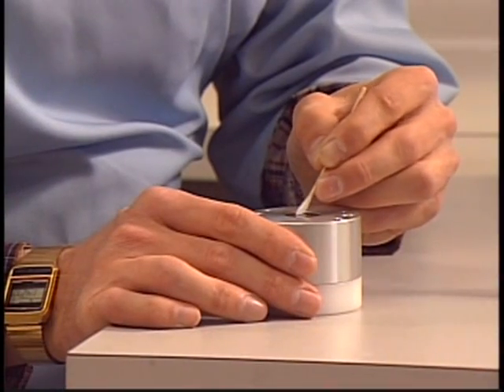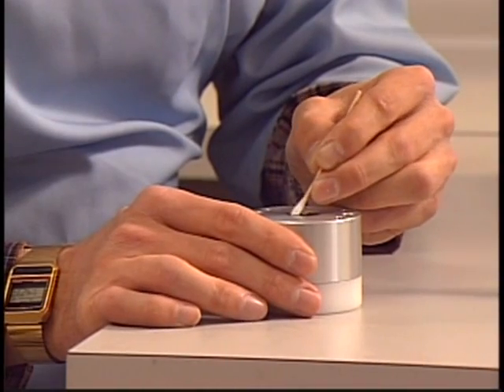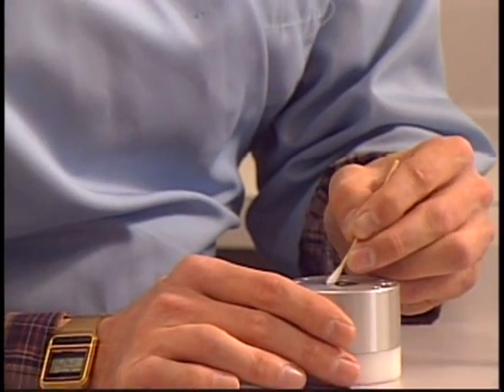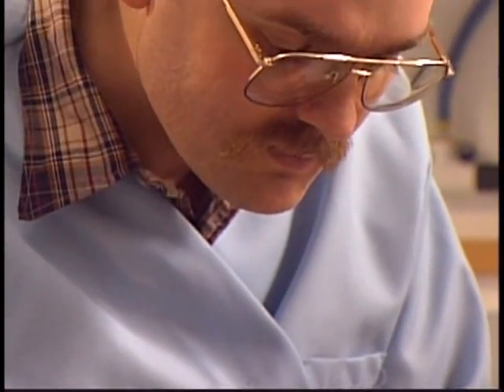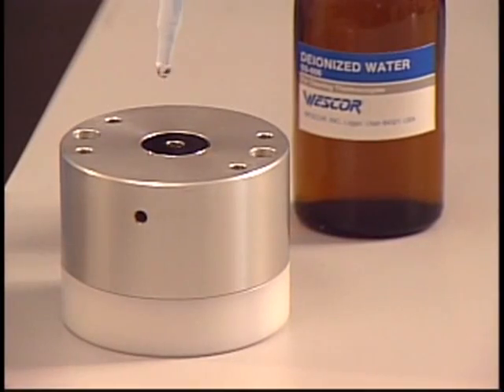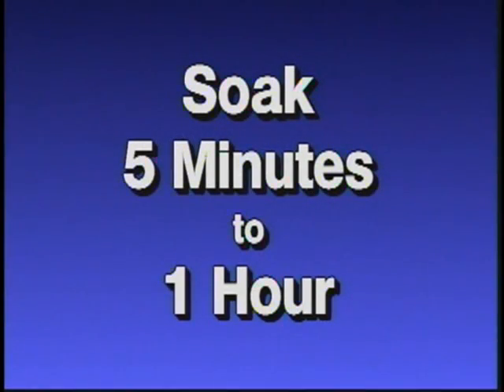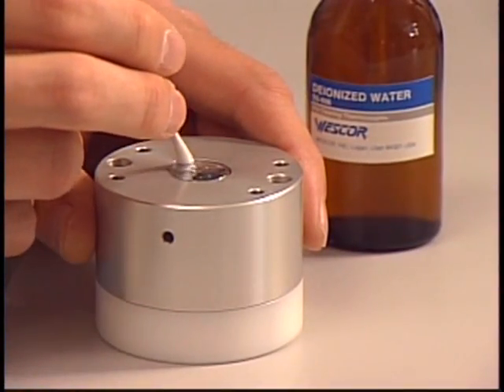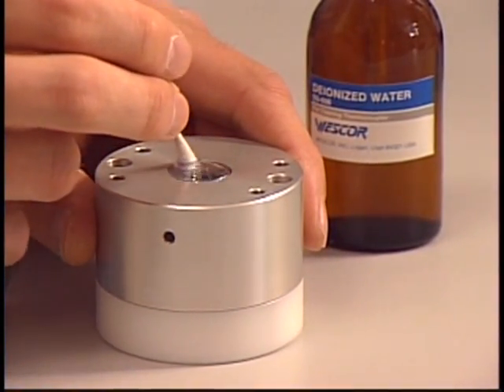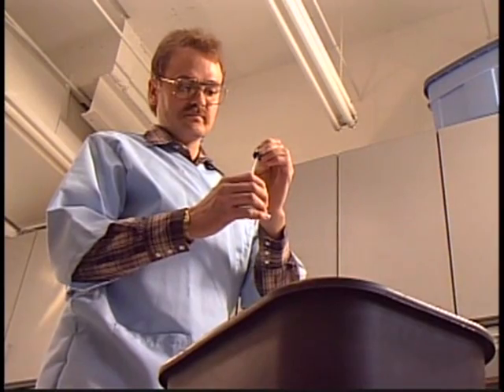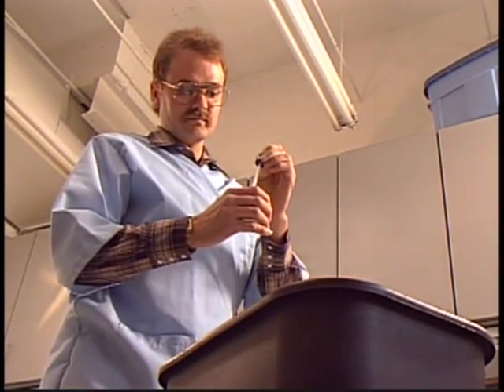With the thermocouple out of the machine, wipe around the thermocouple mount with a dry swab to remove any oily residue. Be careful not to snag the thermocouple. Next, place a few drops of deionized water on the thermocouple mount. Simply let it soak for at least 5 minutes to even an hour while you go to lunch. Now take a swab and wipe around the mount. After that, you're ready to rinse. Drop on deionized water and shake it off. Drop on, shake off, at least 10 times.